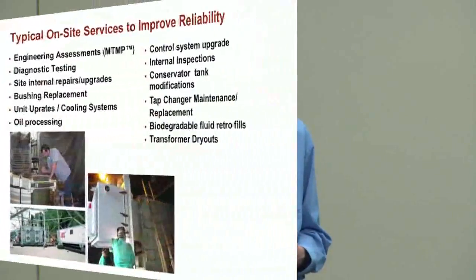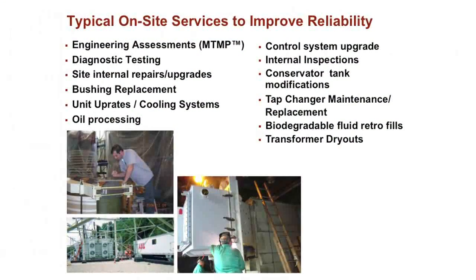Doing modifications on the conservator. What we usually mean by that is that a lot of transformers are designed to be free breathing, meaning when the oil expands and contracts, it's just taking air in and out from outside. But you can change that so it has a system where it's not exchanging air with the outside. The good thing about that is you don't get oxygen in the oil, and then it reduces the aging rate of the cellulose.